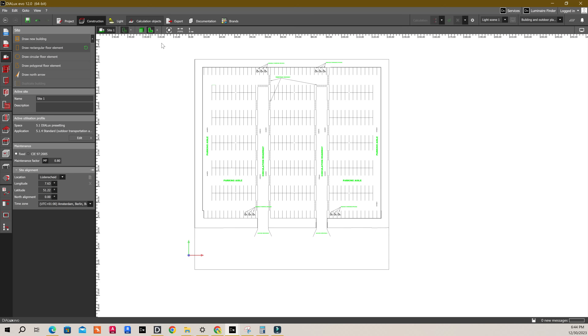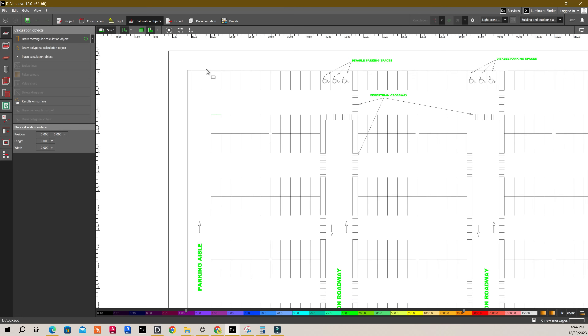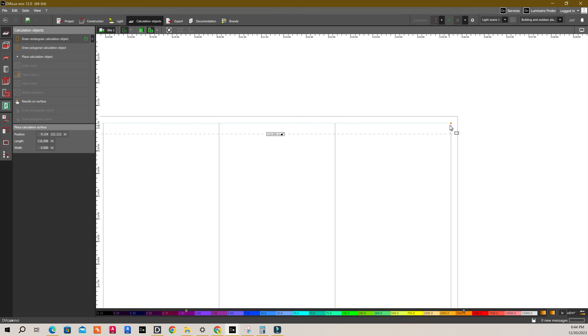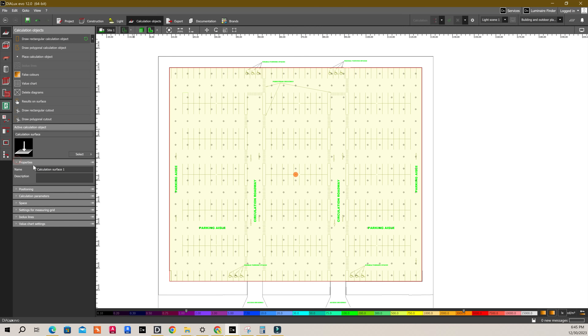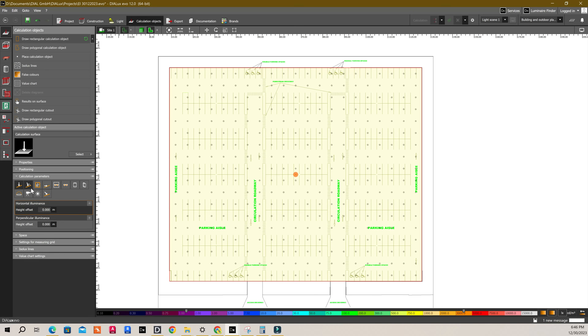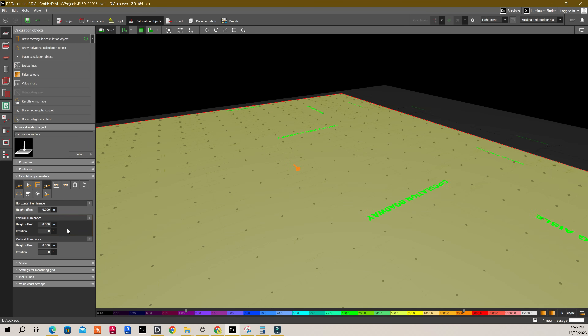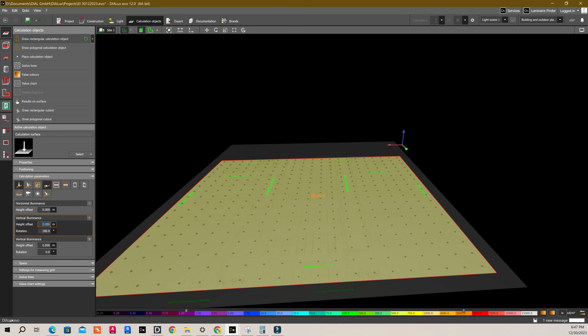Now, we have to draw a calculation object for all these areas. Click on calculation objects, then click on draw a rectangular calculation object and draw one for the overall car park. After this, rename it to 'car park all areas' in the property section. In calculation parameters, set one horizontal illuminance. Also, we need two vertical illuminance, so I am adding one more by clicking the plus option — one horizontal illuminance with arrow facing downwards to the ground, and one vertical illuminance with arrow facing left, which is 180 degrees at 1.5 meter chest height. The second is with arrow facing to the right, which is 0 degrees at 1.5 meter chest height.